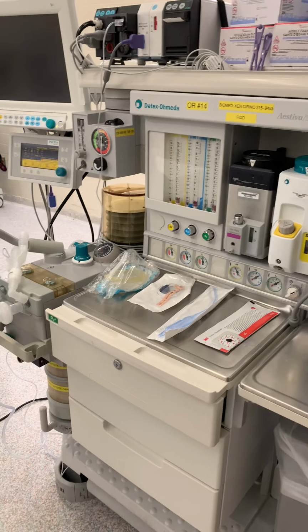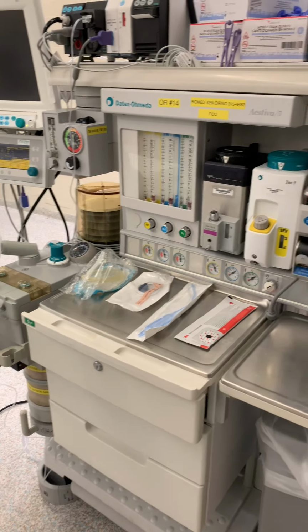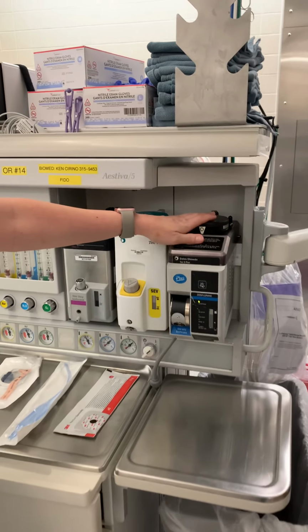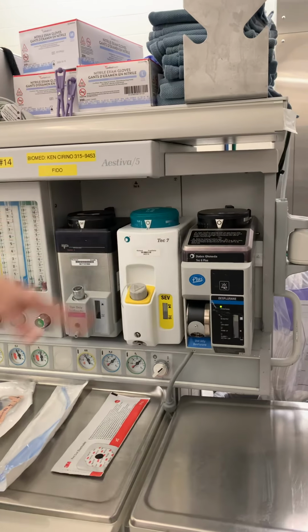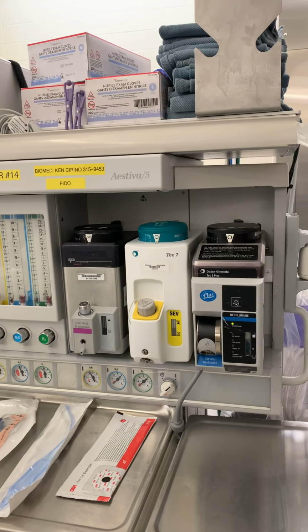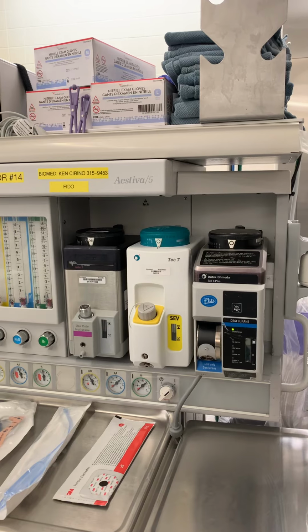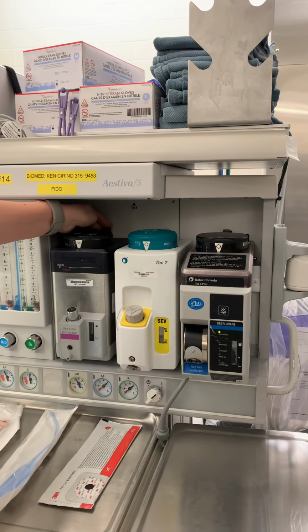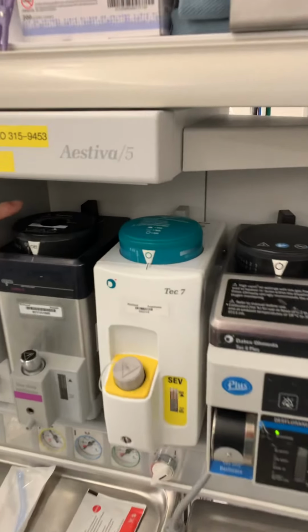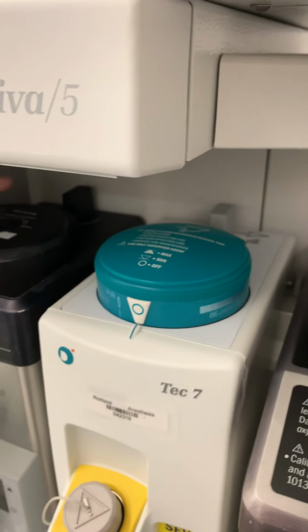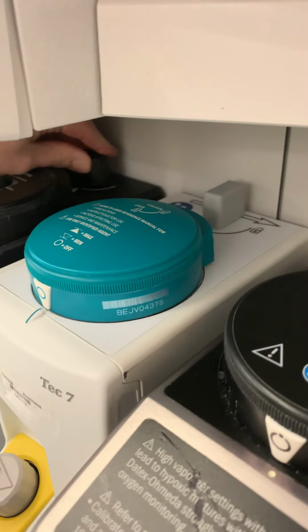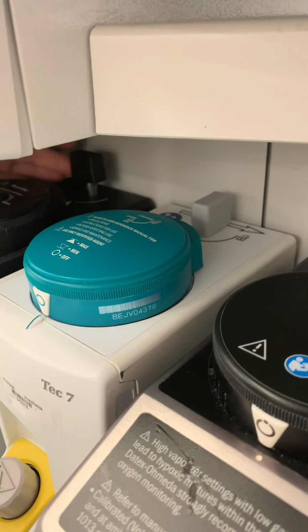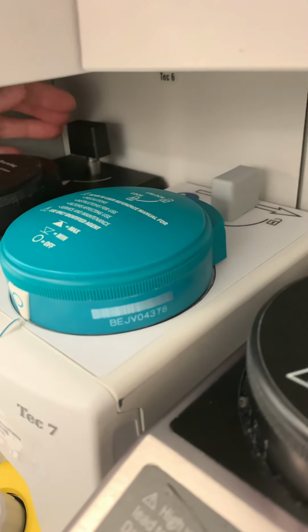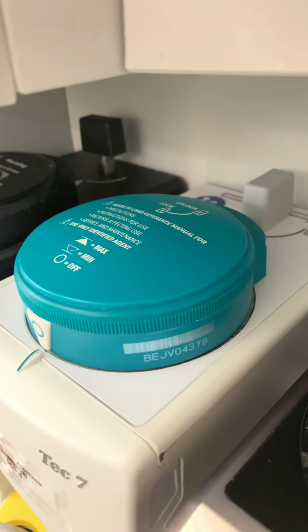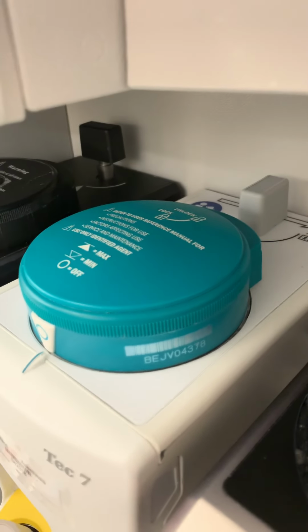Number 4, we want to check the vaporizers. That entails taking a general look at them, making sure that they're all nice and flat, and that they don't look crooked. That just means that they're seated properly on the manifold. You need to make sure that they are locked into place. If you look way back, you'll see that there's a locking mechanism, and to unlock, you turn it 90 degrees to the right, and it will turn and pop up, and it means it's unlocked. At this point, you can lift the vaporizer off the manifold.